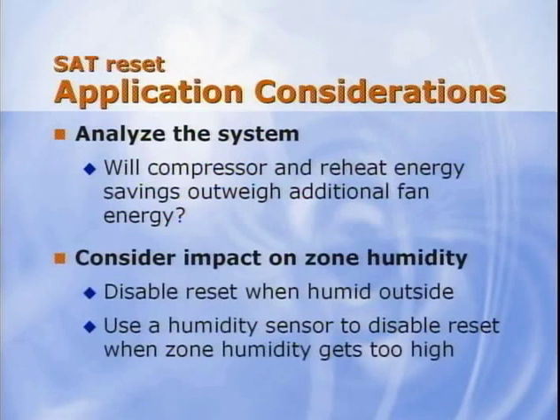If higher space humidity levels are a concern, consider either disabling reset when it's humid outside or provide one or more zone humidity sensors to override the reset function if humidity in the zone exceeds some maximum limit.